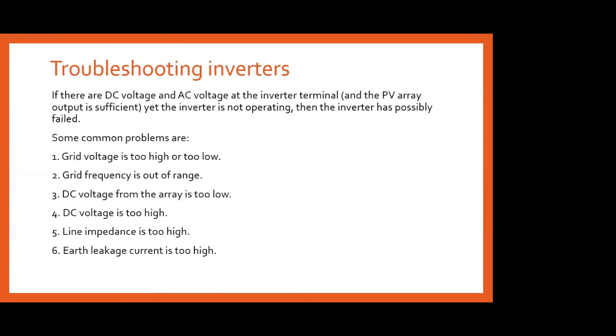Of course, what about troubleshooting when it comes to the inverters? The inverter is connected on both sides: one is the DC voltage side, the other is the AC voltage side. If there is any problem with the DC voltage, then we have to monitor starting from the PV arrays to the combiner boxes, fuses, and all those things. If there is any problem with the AC part, from the grid to the AC connections, that is, to the output of the inverters, all those things have to be checked.